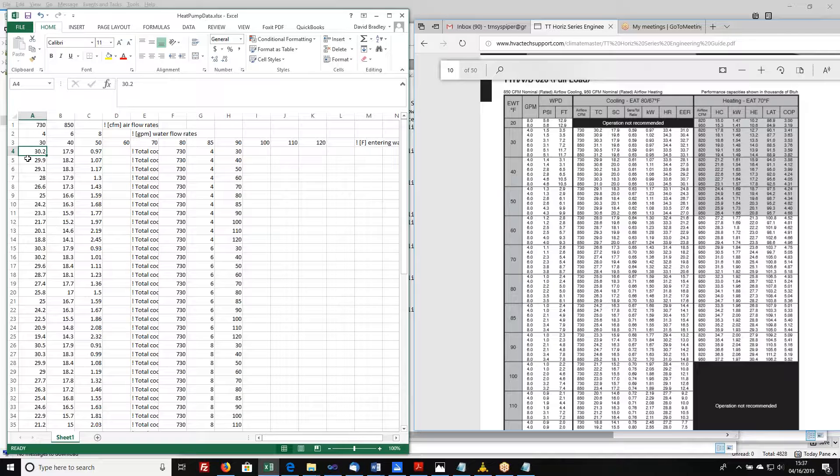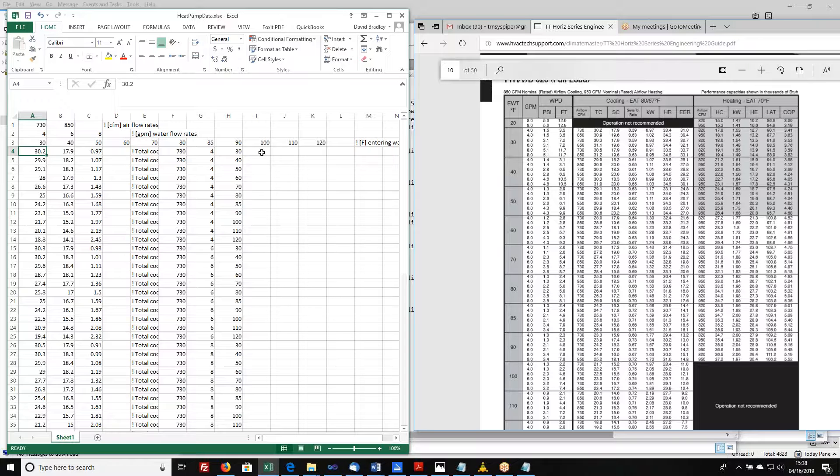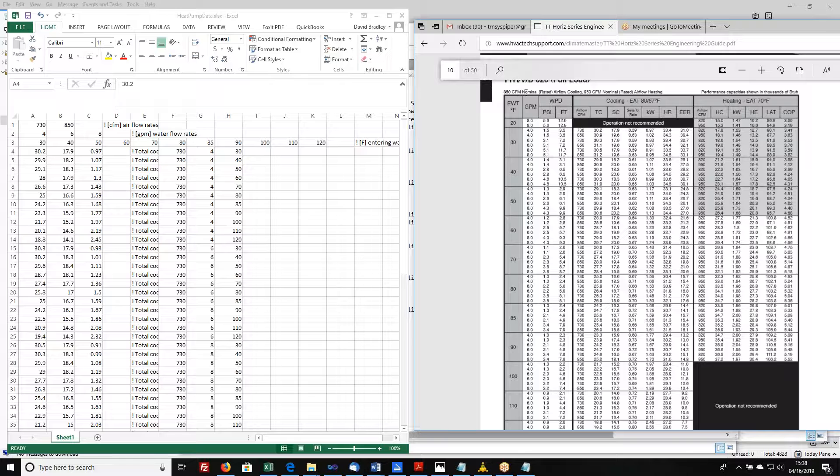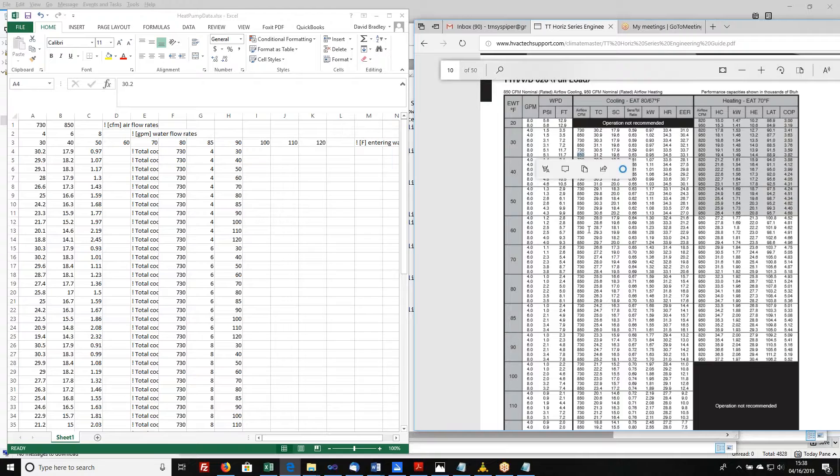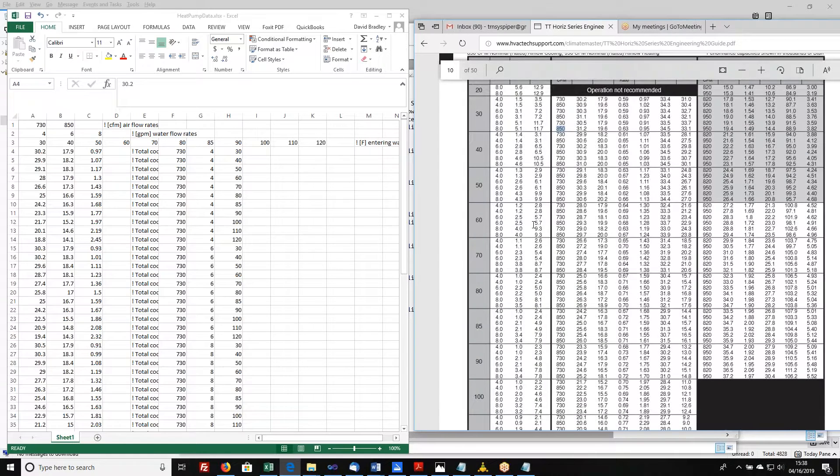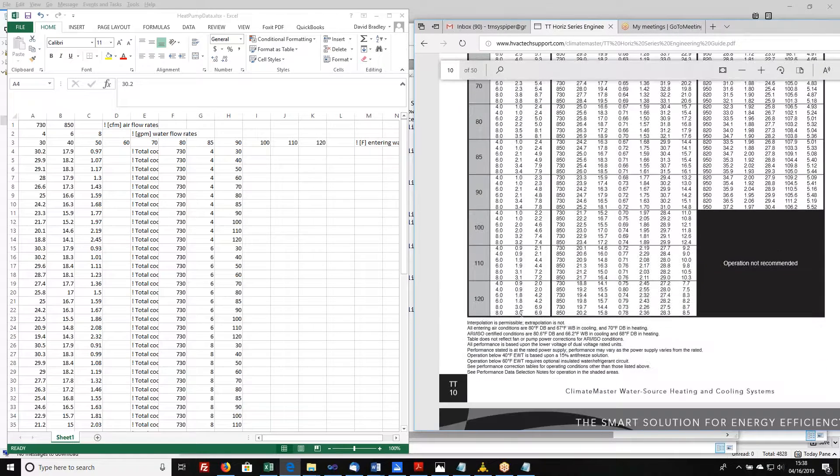What we mean is that every point in here is going to be divided by the total capacity at the heat pump's rated condition. Once you normalize these data files, they tend to look very similar to one another. Then just by changing the rated values, the rated total cooling capacity, the rated sensible capacity, and the rated power, it makes it very easy to quickly change heat pump sizes. So we have to figure out what the rated condition is. And oftentimes there will be a few clues in the data file. Now, you see right up at the top here, hopefully it's clear enough on your screen, but it says 850 CFM nominal rated airflow in cooling. So we know that in cooling, it's these 850 CFM values, one of which is going to be the rated condition. Sometimes you can go and look in a standard and they'll reference which standard it comes from.